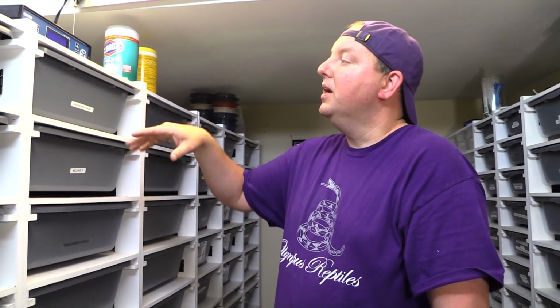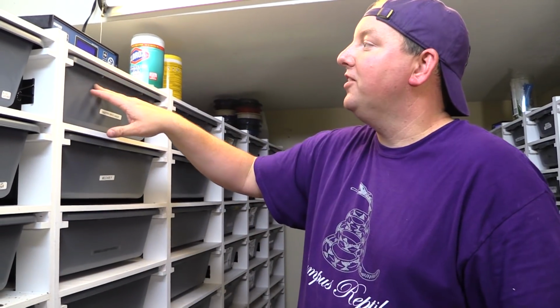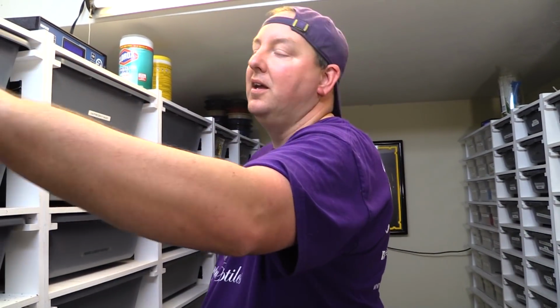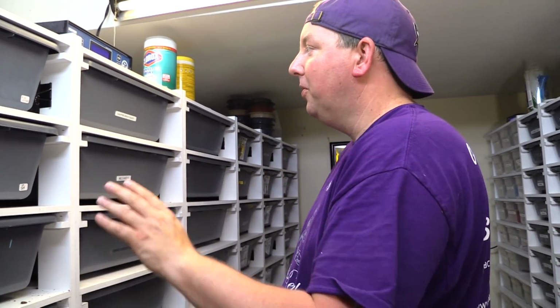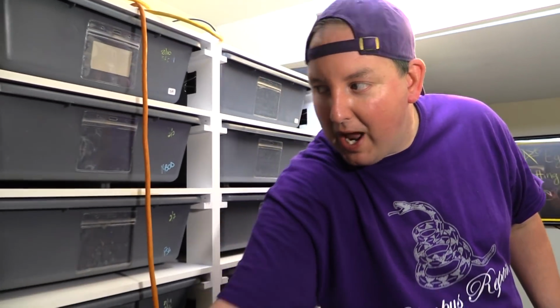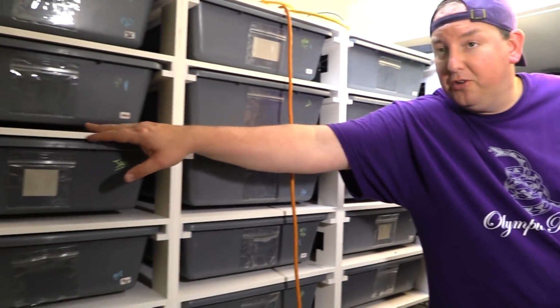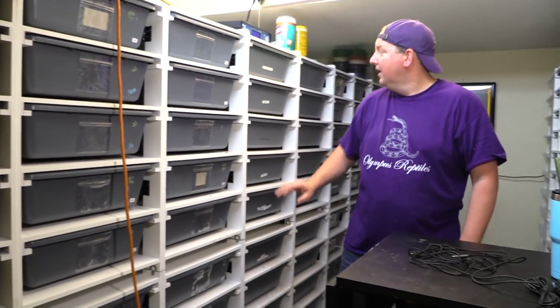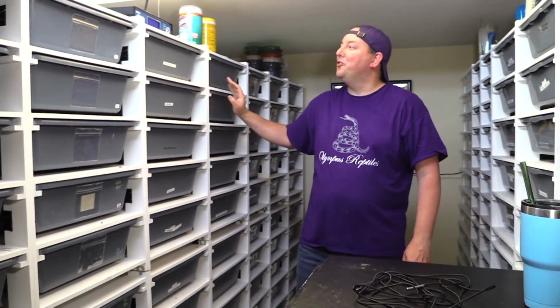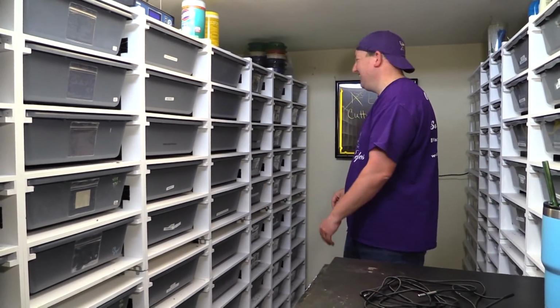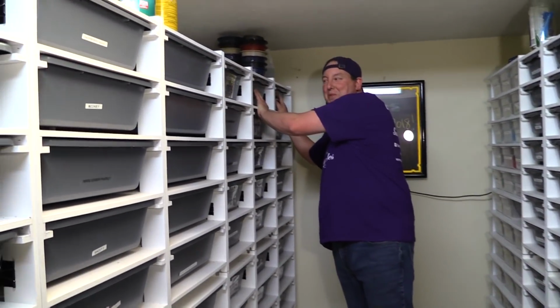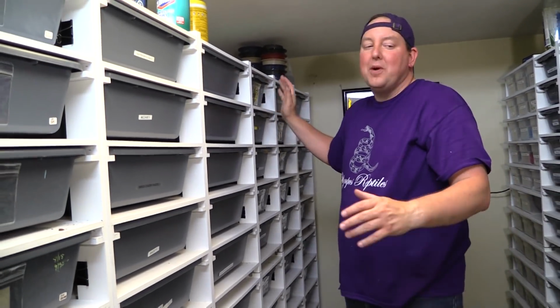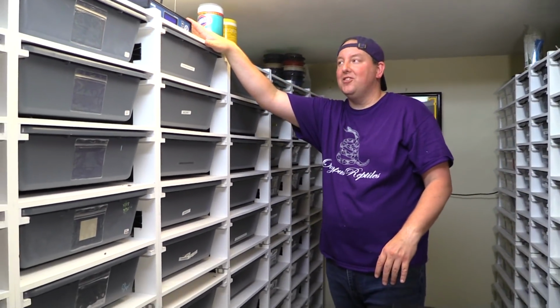The other thing about that too is not only will it fail in the off position on these 6s, but each probe is fused separately. So each plug-in in the back is fused separately. So if there's a problem on probe 1, only probe 1 shuts down. Probe 2, probe 3, probe 6 will continue to run. And what's running is probe 1 is running those entire 2 racks. These 2, or this one will be probe 2. These 2 will be probe 3. This is probe, or excuse me, I went backwards. Got something new. So these 2 are probe 1. This is probe 2.